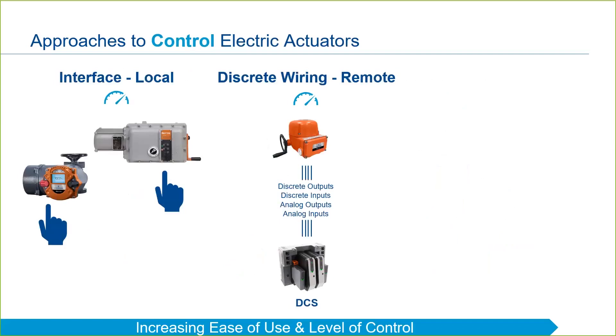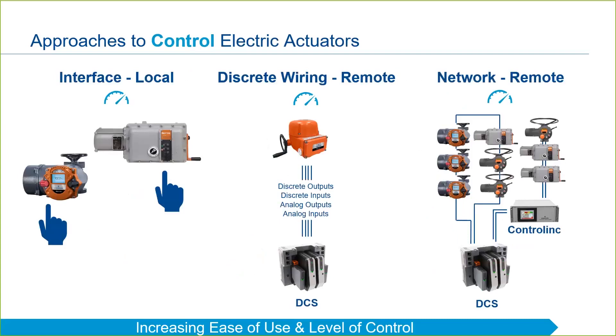That leads us to the last approach to controlling electric actuators, which is through network control. Typically, networks run on a single pair of wires and they communicate via Modbus, Fieldbus, Hart, Profibus, or other common industrial protocols. Wiring costs are lower as multiple actuators can be put onto the same network loop. Rather than running all loops back to the control room, some customers prefer to install a Controlinc network master in order to offload some of the burden from the DCS system.